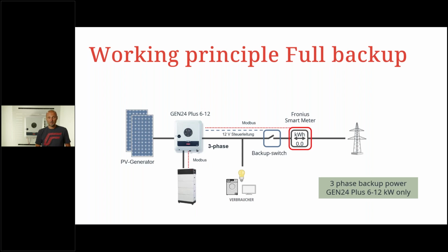In the full backup, you see that we have a backup power switch required. So two additional components, basically the battery, of course, and the backup power switch. The backup power switch can be different components. I will show you later which components you need. Take care that if you have a GEN24 Plus, only the 6 to 12 kilowatt units work. On all Primo and Primo Plus inverters, it would also work, and also the Symo 6 to 12 kilowatt would work with it.